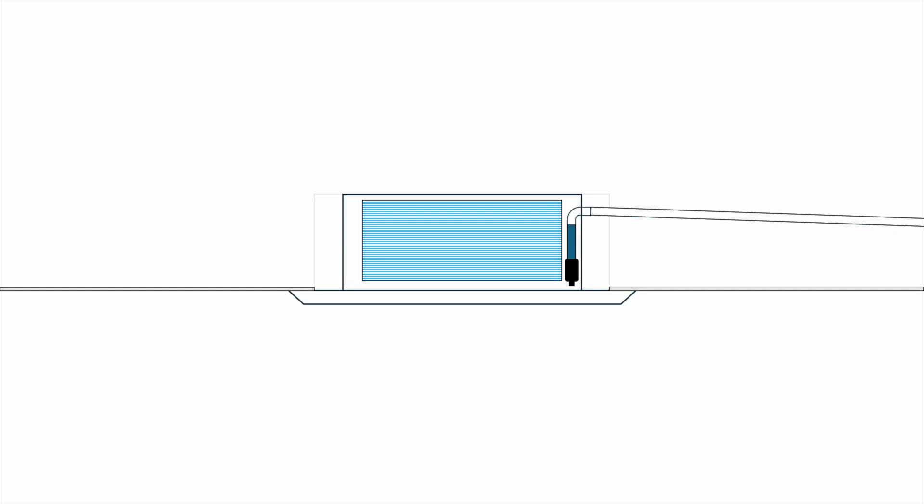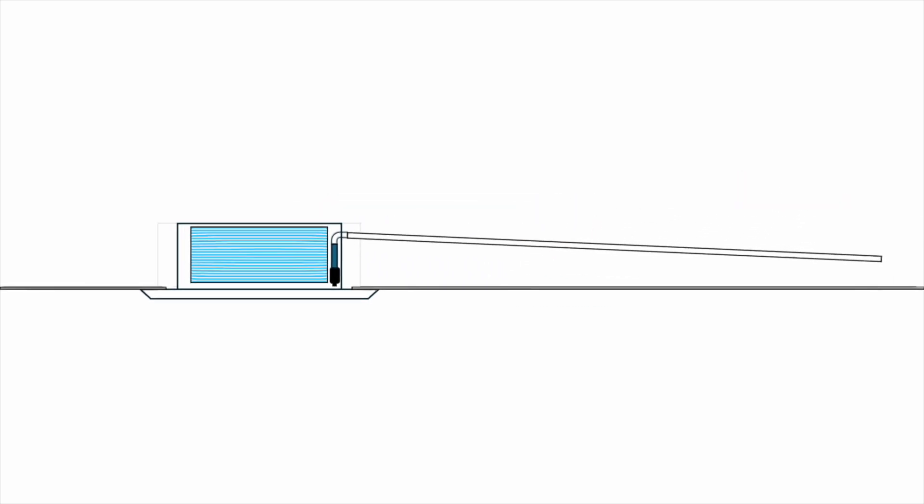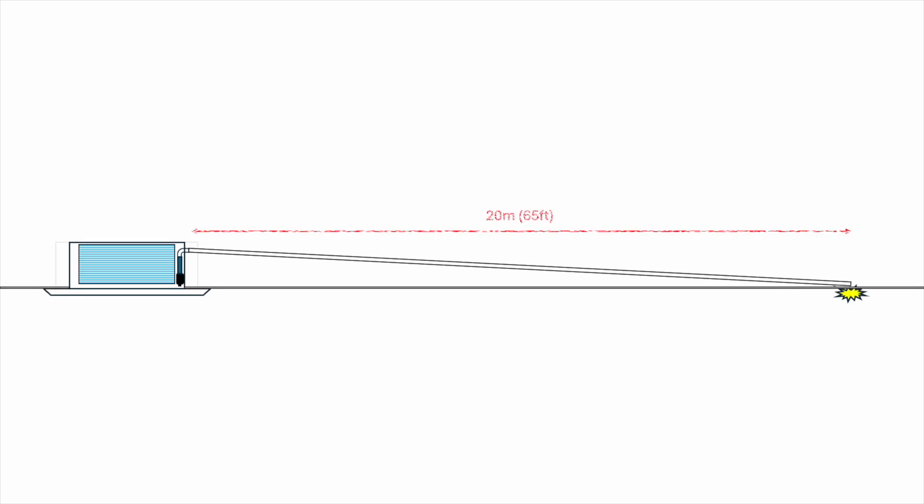However, there is a problem. A typical ceiling cassette is about 250mm or 10 inches tall. The drain outlet is about 200mm or 8 inches from the ceiling. At a standard slope of 1 to 100, meaning for every 100m of length, the drain pipe must drop by 1m. It takes only 20m or 65 feet before the drain pipe hits the ceiling. In large buildings, it is very common to have the drain pipe run well over 20m before reaching the discharge point. Therefore, it is very difficult to have enough slope while having a long drain pipe.